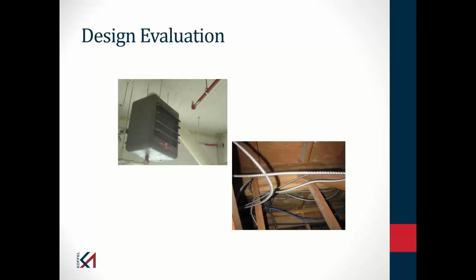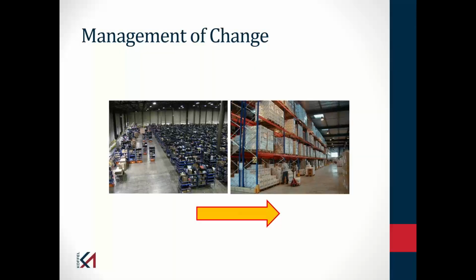We have a new problem, and the committee's still trying to struggle with this. And I'll call it the Amazon problem. You know, Amazon delivers packages and leaves them on the outside of our building. That has caused them to use a cardboard container that is more water resistant. That more water resistant container doesn't allow my sprinkler water to seep through the container, and therefore we're going to get a different fire than what we have in the older cardboard containers. And we're looking at, does that require some different design criteria for the sprinkler system in that space? I don't think most owners are going to realize that. We're going to come back and talk about, well, who's going to do it if the contractor's not doing it and the owner may not have the expertise to do it? So that container is a management of change issue. If you have warehouse space and you're storing something different in that space today, somebody needs to look at that sprinkler system.